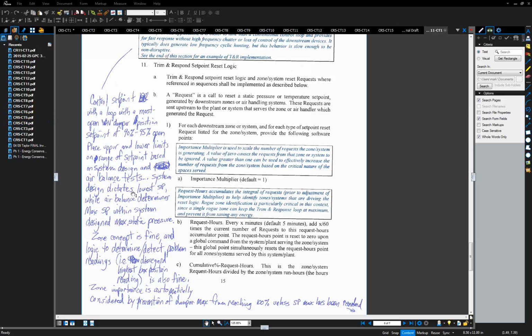The other thing about trim and respond is that if something gets wound up, you can have a nonlinear response. We do a lot of data centers, and as you get zones where the temperatures are rising, it wastes a lot of energy, particularly because the fans on servers are as much as 15% of the overall energy use of the server once they're at high speed. So you want to keep them below that for energy efficiency. Plus, you don't want the servers too hot because you could have failures.